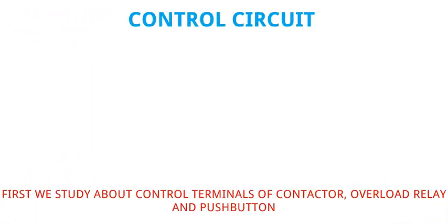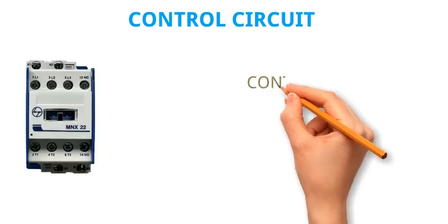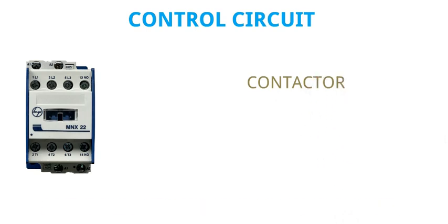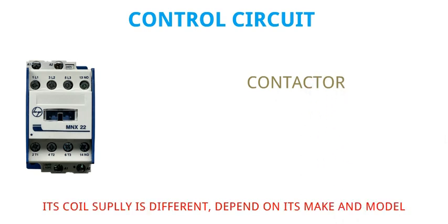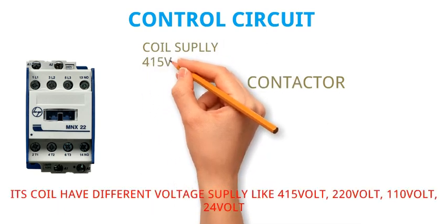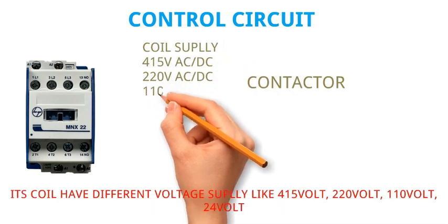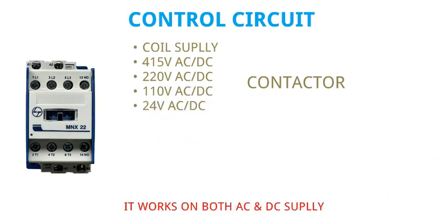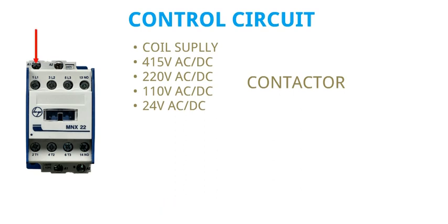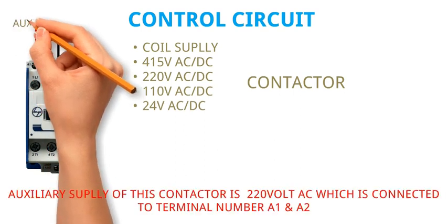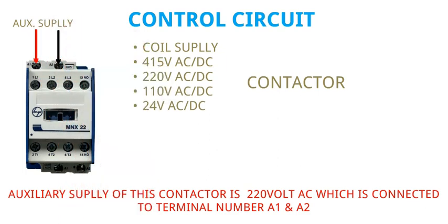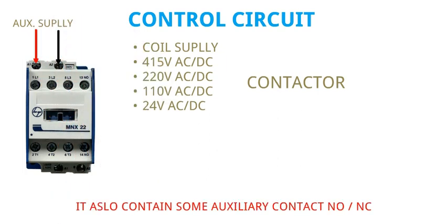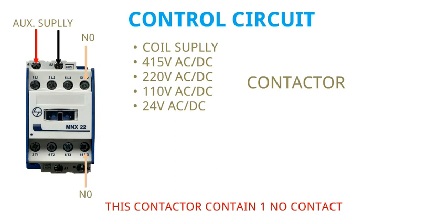First we study the control terminals of the contactor, overload relay, and push button. The contactor coil supply varies depending on its make and model — it can be 415 volt, 220 volt, 110 volt, or 24 volt, and it works on both AC and DC supply. The auxiliary supply of this contactor is 220 volt AC, connected to terminals A1 and A2. It also contains auxiliary contacts — NO and NC. This contactor contains one NO contact.